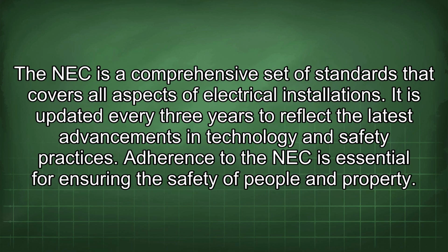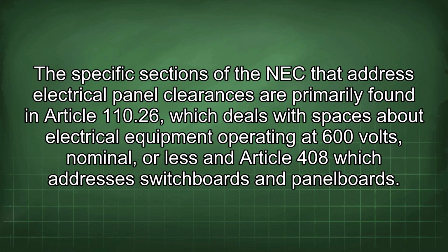The NEC is a comprehensive set of standards that covers all aspects of electrical installations. It is updated every 3 years to reflect the latest advancements in technology and safety practices. Adherence to the NEC is essential for ensuring the safety of people and property. The specific sections of the NEC that address electrical panel clearances are primarily found in Article 110.26, which deals with spaces about electrical equipment operating at 600 volts, nominal, or less, and Article 408, which addresses switchboards and panelboards.